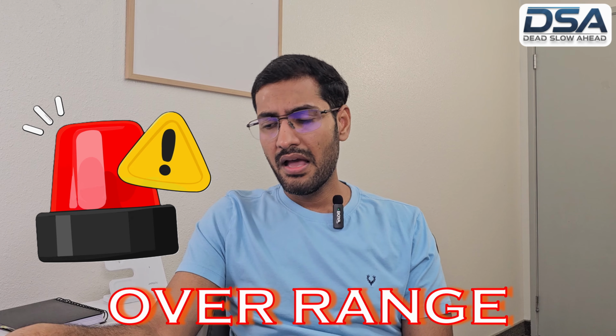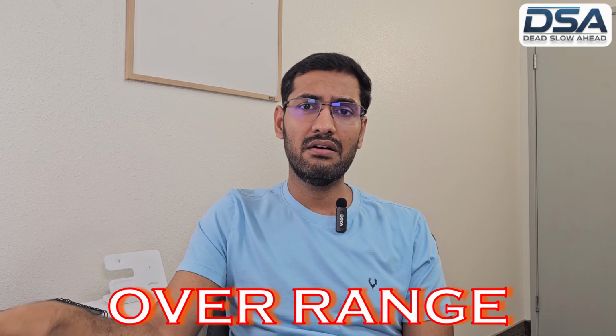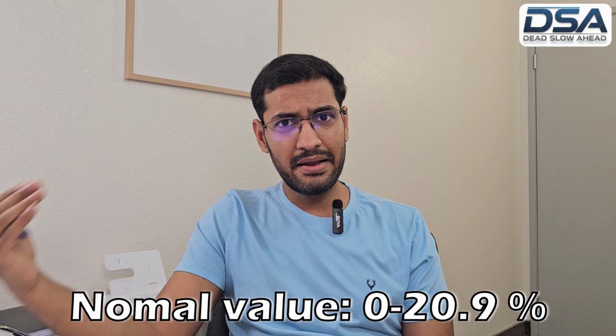So today I'm going to share a troubleshooting case related to an oxygen gas detector on board. Everything was running normally and suddenly our oxygen gas detector triggered an alarm and was showing overrange in our fixed gas detection system panel. Ideally, it should read somewhere around 0 to 20.9 percent oxygen, but this time it was completely out of the limit. This is something that we cannot ignore.